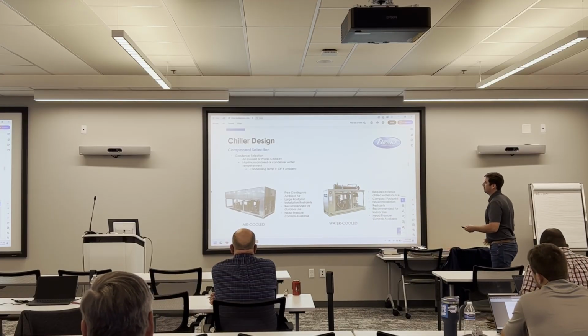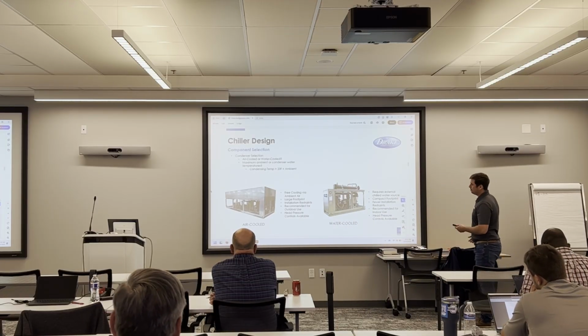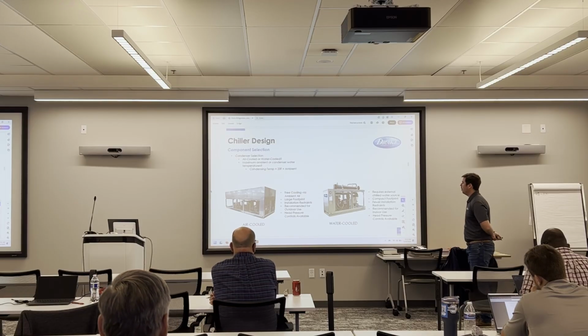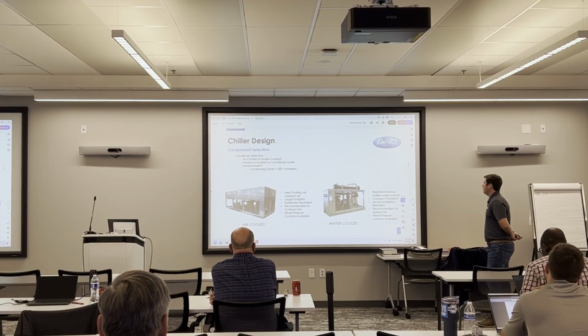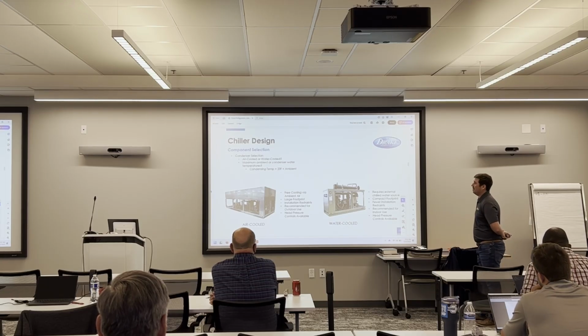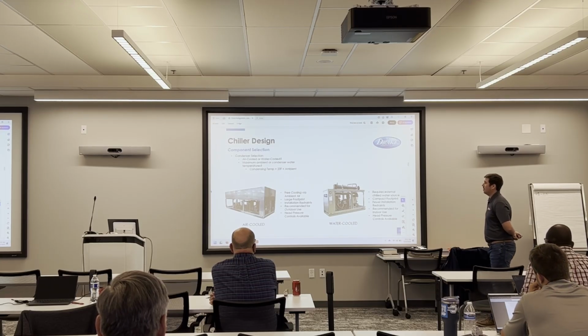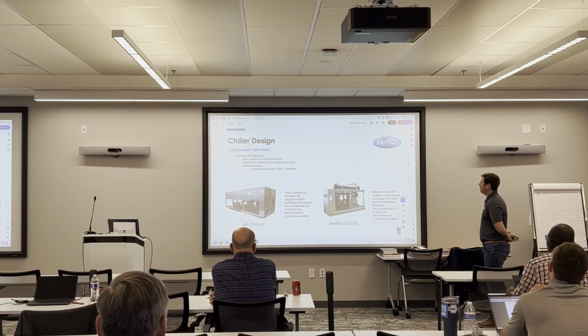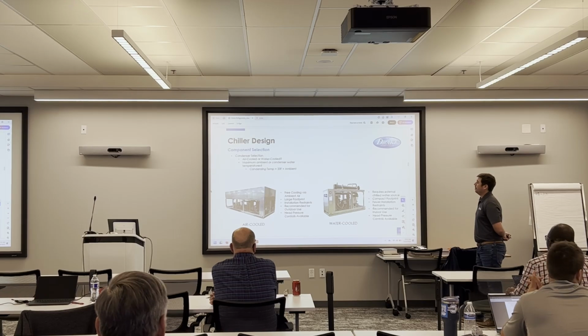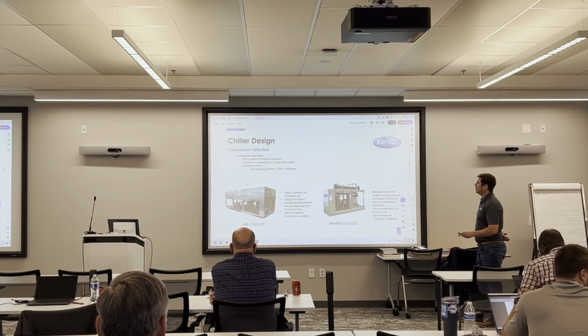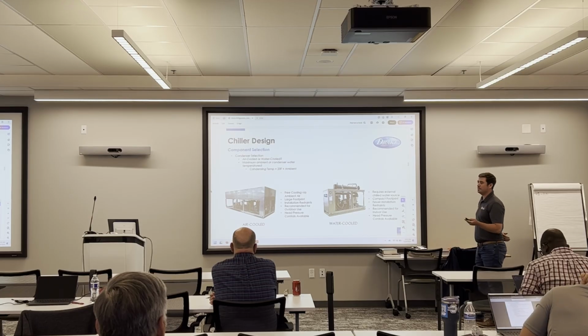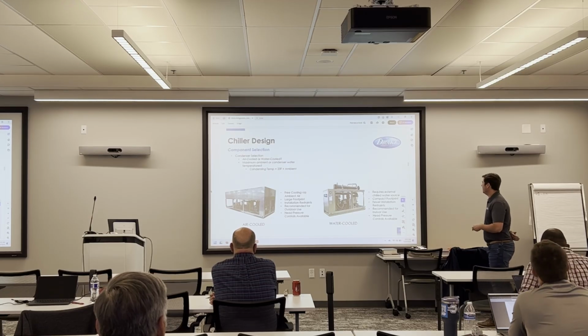Obviously, for a water-cooled unit, we're using an external water source to cool the refrigerant. So it requires an external water source, and a lot of people don't have that. That could be in the form of a water tower, or maybe they're pulling water out of a river if they're next to a river. City water, if you want your water bill to be wicked high. Or if you wanted to, you could get an air-cooled chiller. I've seen people use air-cooled chillers to supply chilled water to a water-cooled unit. Seems redundant, but I guess it works.